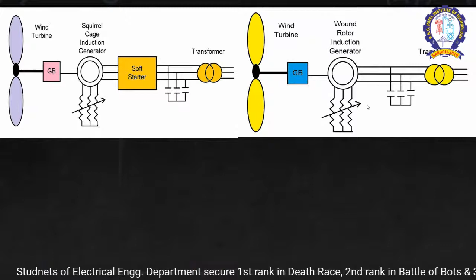The third aspect is known as the doubly fed induction generator, so the power is fed from both directions. This technology is again renowned for wind energy applications. The DFIG can be covered by the stator and rotor itself, because the wind turbine is connected through the gearbox to the rotor and the power is generated through the stator, and the rotor and stator are both connected with the transformer and the grid. We have a controlled rectifier and a controlled inverter, so we can manage the power from both sides. Usually the power is shared 70% from the stator side and 30% from the rotor side.